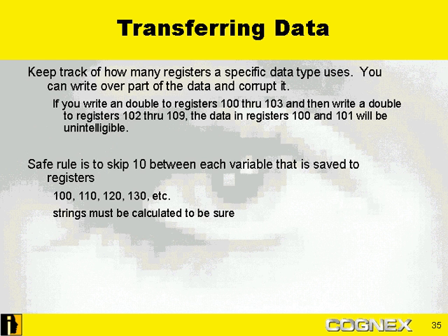You have 16,000 of them, and the likelihood of running out is pretty slim. Usually I start at register 100, for instance. I'll use 100, then 110, 120, all the way up. That means any data type other than string, you'll be all set. If you are using string, there's a function called string.length that determines how many characters are in the string. Then you have an idea of which registers are being written to.